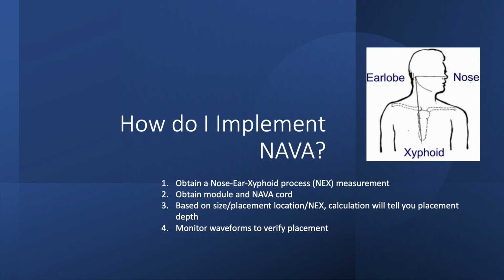When looking to place NAVA on a patient, there's a couple things you need to consider. The first thing that you do is you basically have to run down a module and a cable and place this in a ventilator, because not every hospital that buys Servo i or Servo U ventilators has these modules. You typically have to buy them aftermarket from the company or package deal with them. Once you have this material, you also have to buy a special made NAVA catheter, the OG or NG.